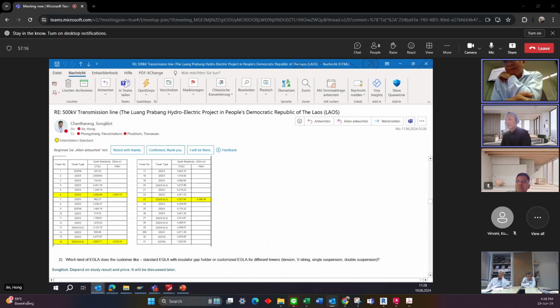Yeah. Our line study and also the thesis have many studies for those cases. It is recommended that if you have a high footing resistance on one tower, you also install the EGLA or line surge arresters on the neighboring towers, because even if the neighboring towers have less footing resistance, due to the back flashover effect their flashover risk will also increase. So it's better not to install on one tower to cover the neighboring ones. But if you have one critical tower, then you need to also install the EGLA on 3 towers, left and right. Yeah, the line study result supports those recommendations.